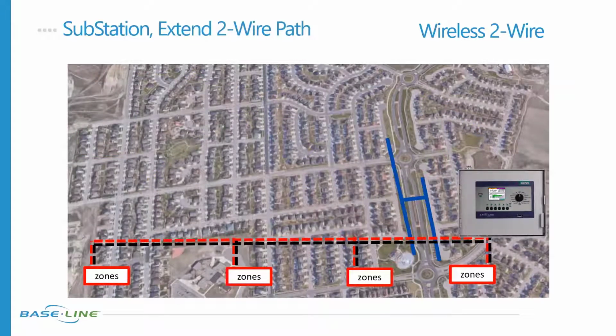A substation can be used to extend the two-wire path. Here we've got zones in multiple places along this two-wire path. There's a finite limit to how far you can run a wire, depending on the wire size—generally 5,000 feet, up to 8,000 feet with a larger wire size. People have been known to go over that limit, either by mistake or because the site grew and they didn't pay attention to the limitations as they added on.